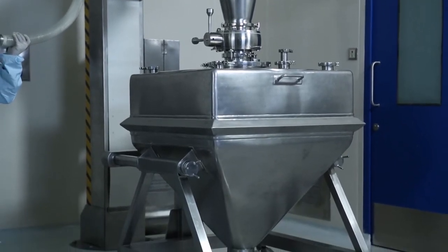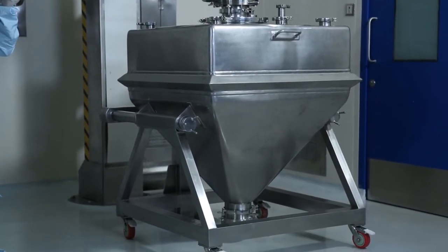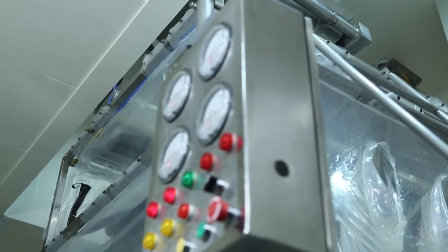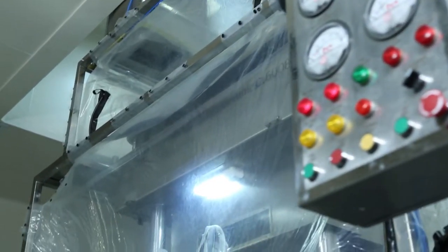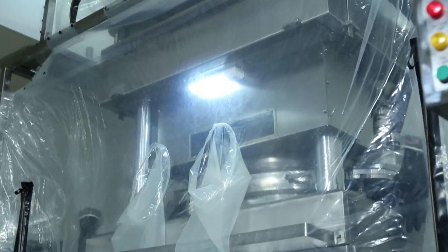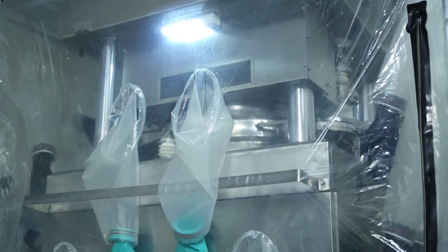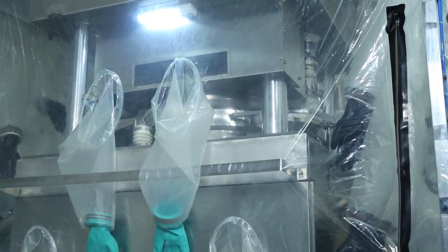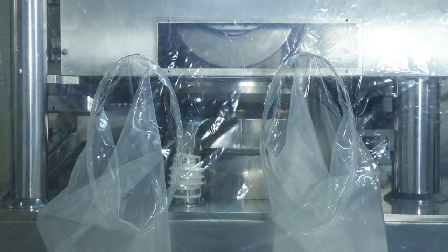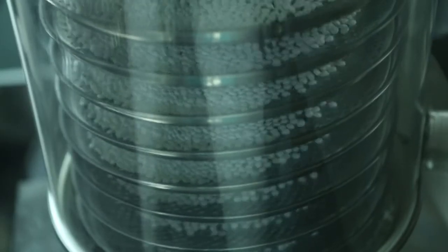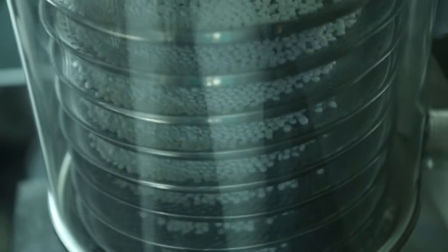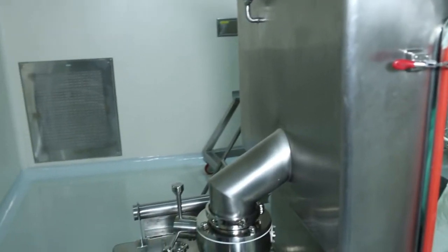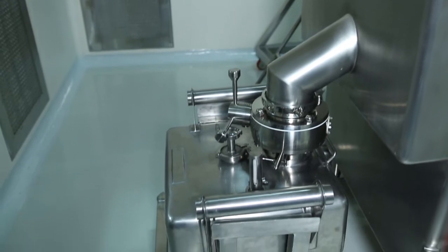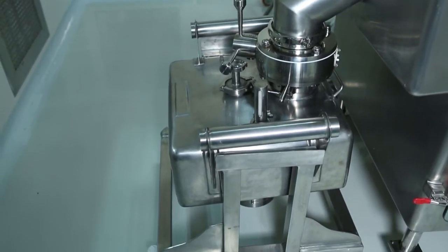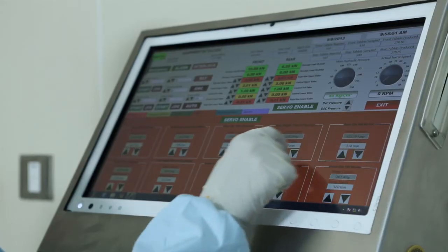The in-process bulk container containing approved lubricated granules is docked to the compression machine in the ISO class 6 area, maintaining containment. The machine is enclosed in a flexible isolator with negative pressure, while the de-duster and metal detector are enclosed in a rigid isolator. Compressed tablets are collected in the bin attached to the isolator. The entire process is controlled by PLC and HMI with access control.